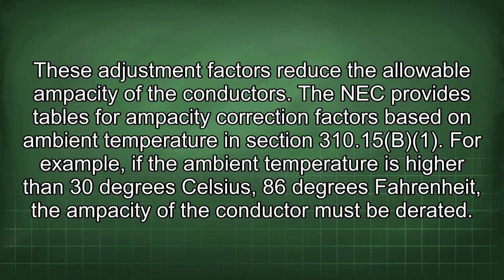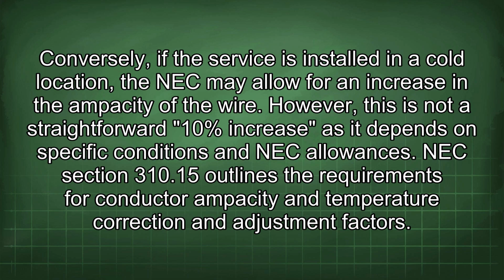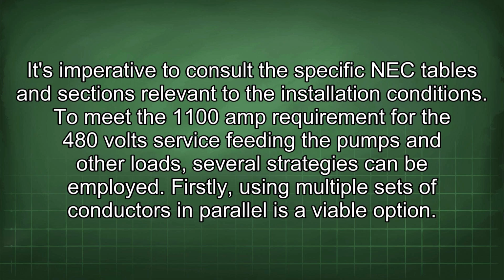For example, if the ambient temperature is higher than 30 degrees Celsius, 86 degrees Fahrenheit, the ampacity of the conductor must be derated. Conversely, if the service is installed in a cold location, the NEC may allow for an increase in the ampacity of the wire. However, this is not a straightforward 10% increase, as it depends on specific conditions and NEC allowances. NEC Section 310.15 outlines the requirements for conductor ampacity and temperature correction and adjustment factors. It's imperative to consult the specific NEC tables and sections relevant to the installation conditions.